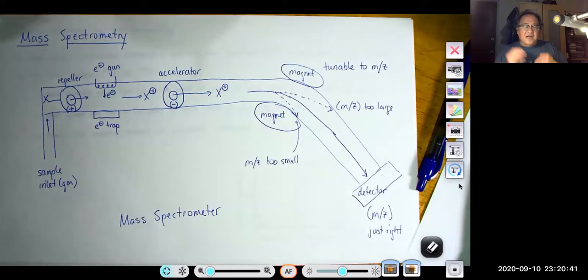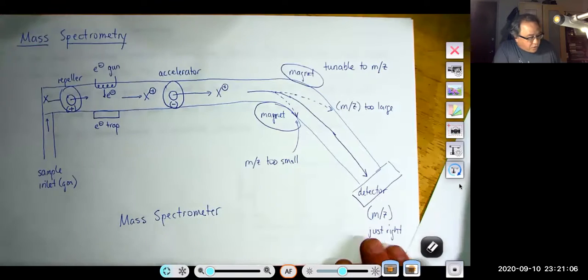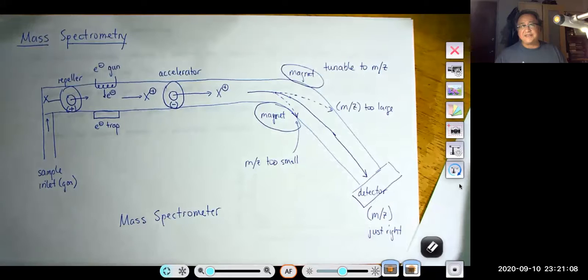So therefore, in that time frame, if you get nothing hitting it, then you say, well, I've got none of that mass to charge. In that same time frame, if you get 2 hitting it, you've got 2. If you get 4 hitting it, you've got 4. So if you look at the 4 versus the 2, the 4 has twice as many proportional isotopes as the 2. So you go through all of these mass to charge ratios, and it takes you less than a second to do 1,000 different mass to charge ratios.